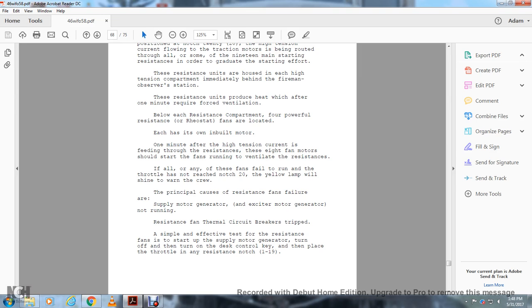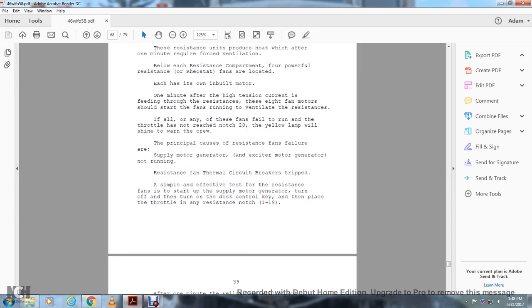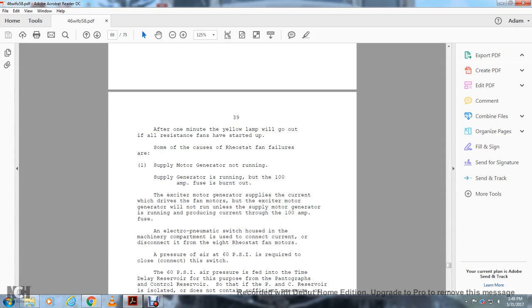The principal causes of resistor fan failure are the supply motor generator or exciter motor generator not running, or resistor fan thermal circuit breakers tripping. A simple, effective test of the resistor fans is to start up the supply motor generator, turn it off, then turn the desk control key on. Then place the throttle in the resistor notches 1 through 19. After 1 minute, the yellow lamp will go out with all the resistor fans started up.